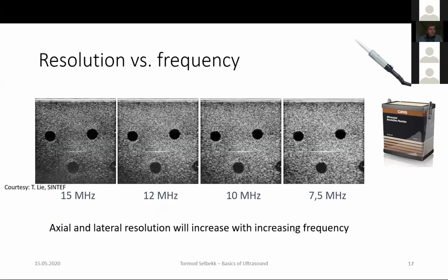When it comes to resolution, it is affected by the frequency. So here we have used a hockey stick probe from BK and an ultrasound phantom and did ultrasound imaging at different transmit frequencies. And you can see that you will have a sharper and more crisp image of the structures with higher frequencies compared to lower frequency. And you also see that the speckle pattern changes, right? Remember that the speckle pattern is also dependent on the frequency. But in general, axial and lateral resolution will increase with increasing frequency.